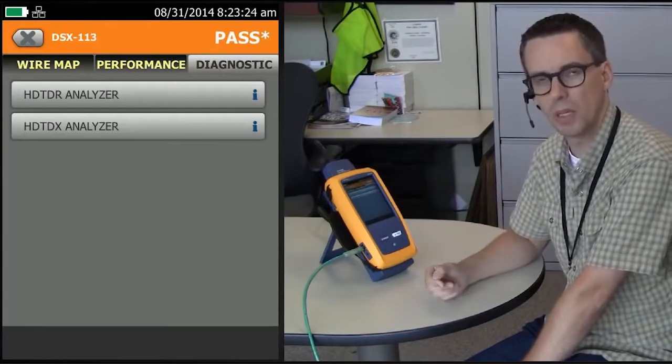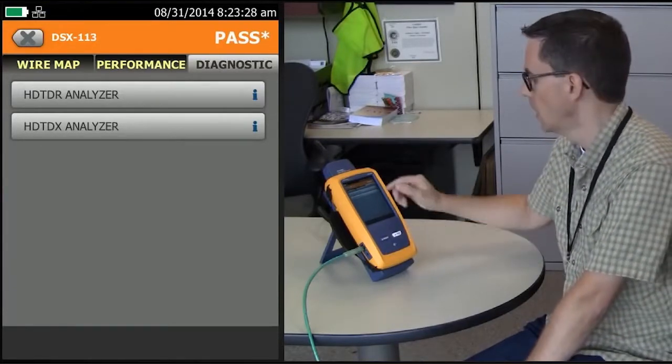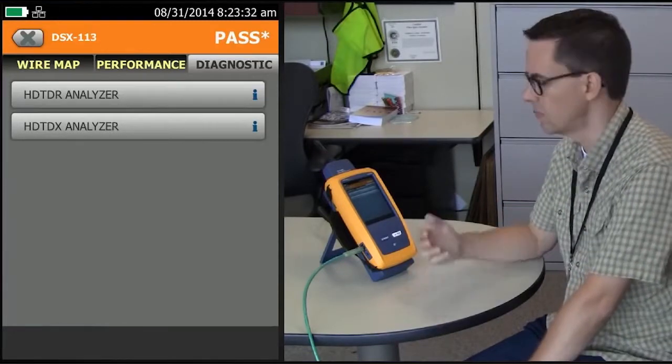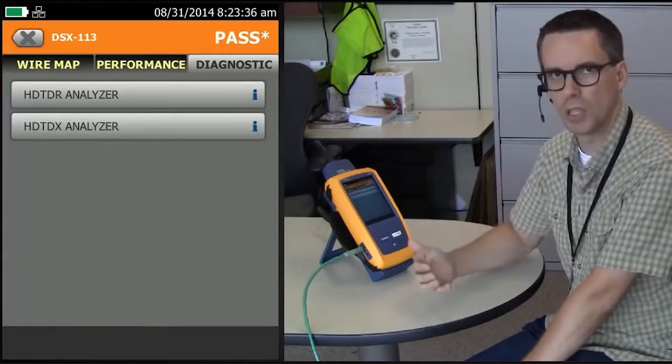I've got two time-domain diagnostic options. That's the ability to look down the cable. The first one is my high-definition time-domain reflectometer, or, I like to say, return loss. It's a good way of remembering that that's for return loss.